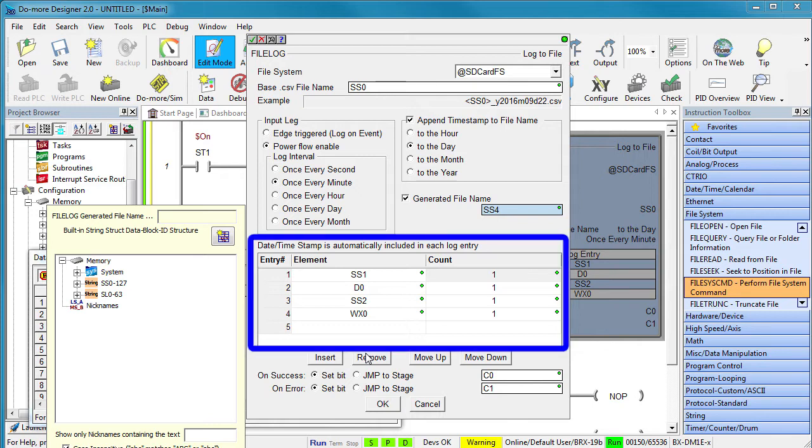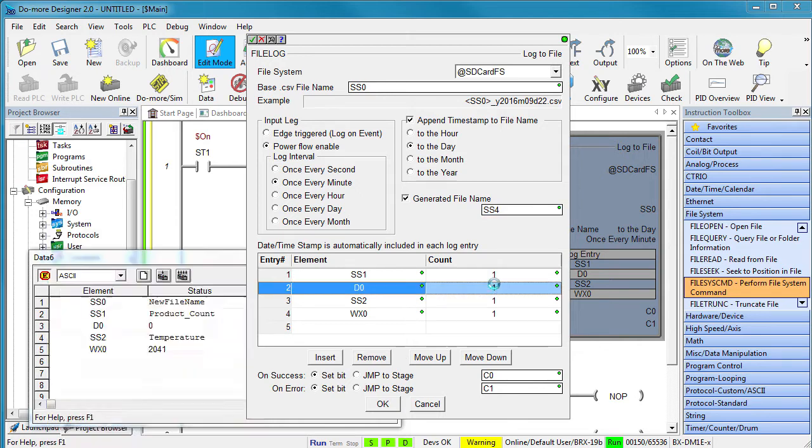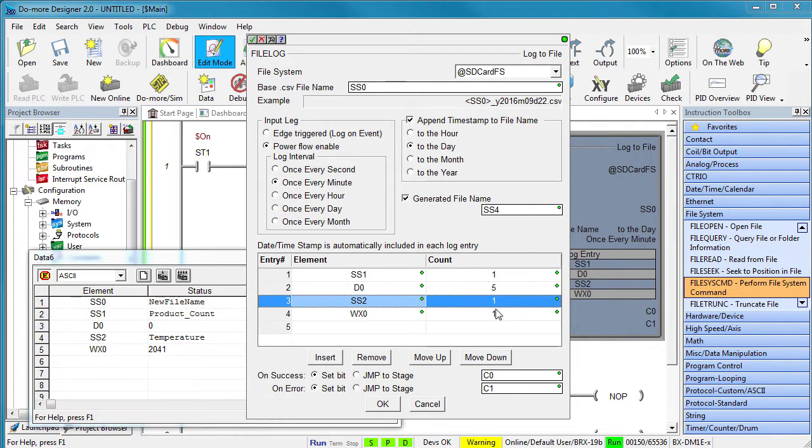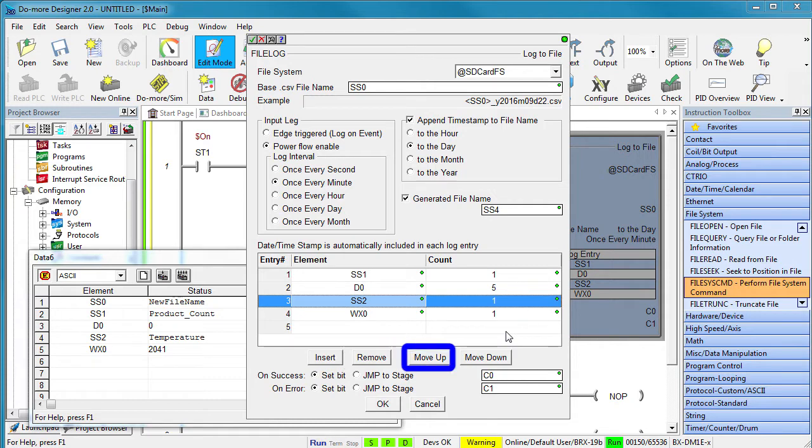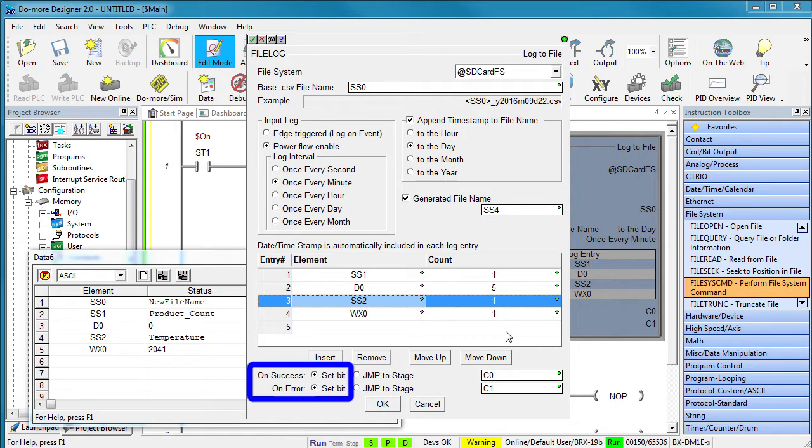You've already seen how easy it is to use this table. Just put whatever you want to log in here. Easy. The count is simply how many consecutive elements you want to send. If we wanted to log D0 through D4, we would have put a 5 here. You are limited to a maximum of 10 consecutive elements per row of this table. And you can insert a row and remove a row and move rows up and down. Very easy to work with. This instruction works great in a stage program, which I personally prefer because it's so easy, but you can also do your own interlocking using the C bits if that's your preference.